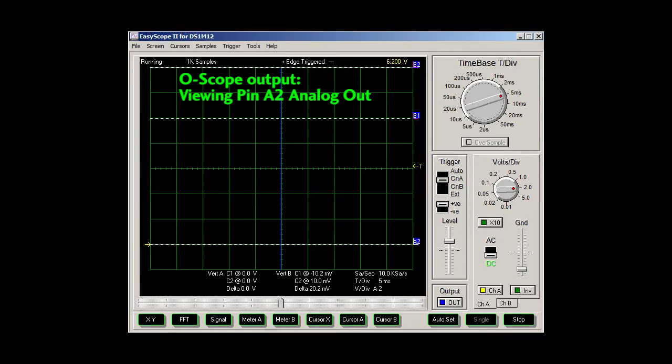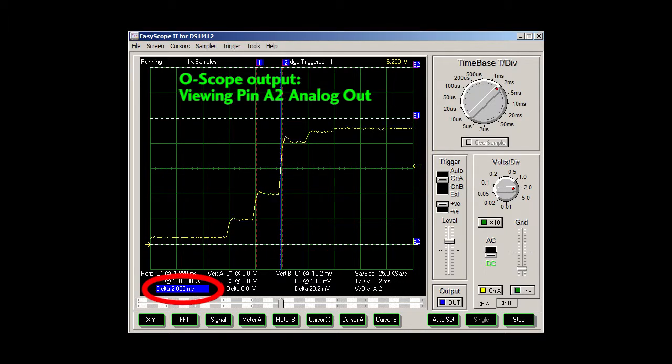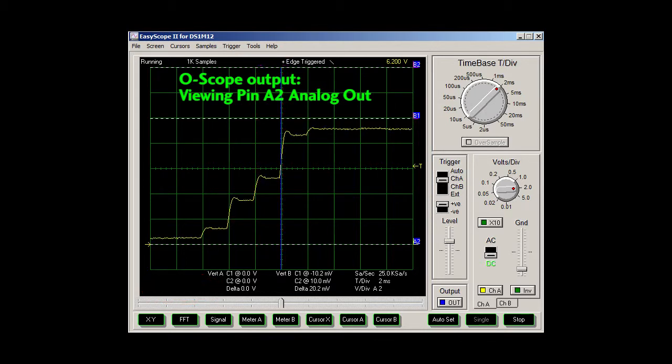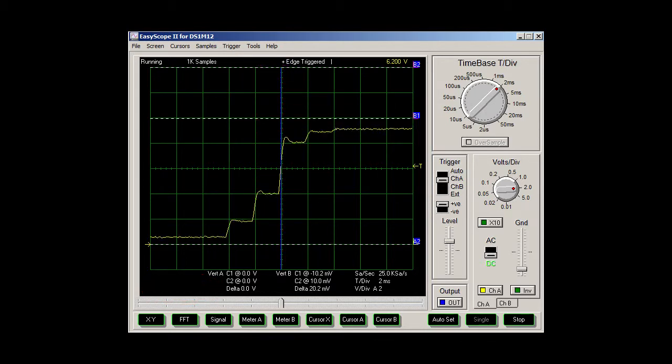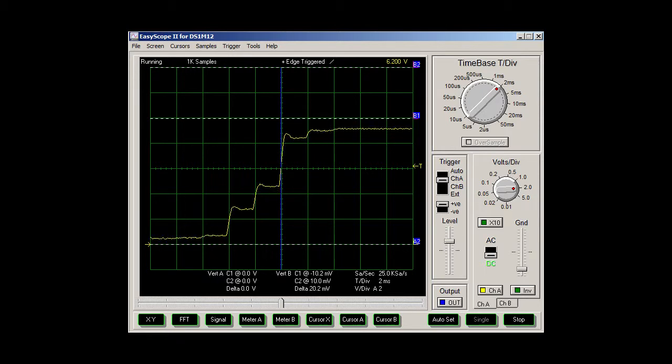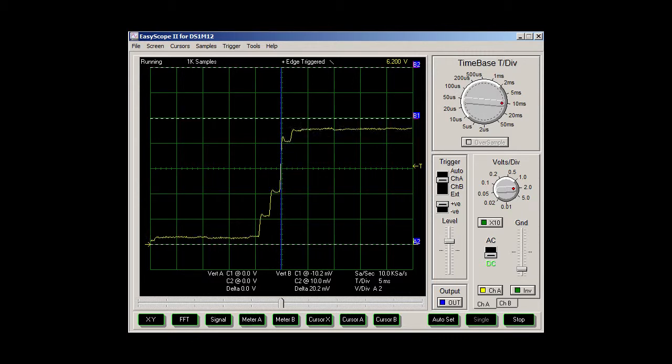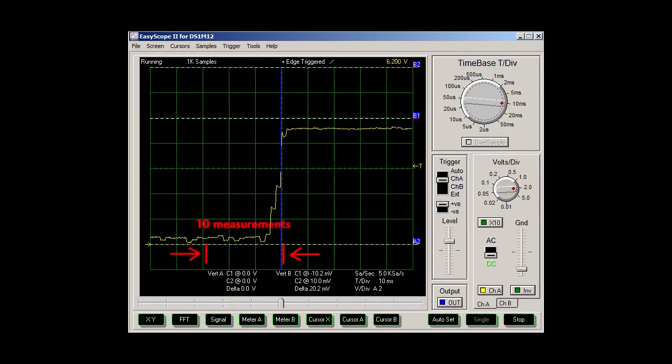If we zoom in, we can actually see each measurement takes 2 milliseconds. With filtering, you can tell the sensor to average 1 to 500 measurements. Selecting 1 tells the sensor to take 1 measurement and output the result every 2 milliseconds. If I change filtering to 2, then that says take this sample plus the previous one, average those and output that result. If the filtering is set to 10, take the previous 10 samples, average those, and so on. Filtering is just how many measurements you want to average.